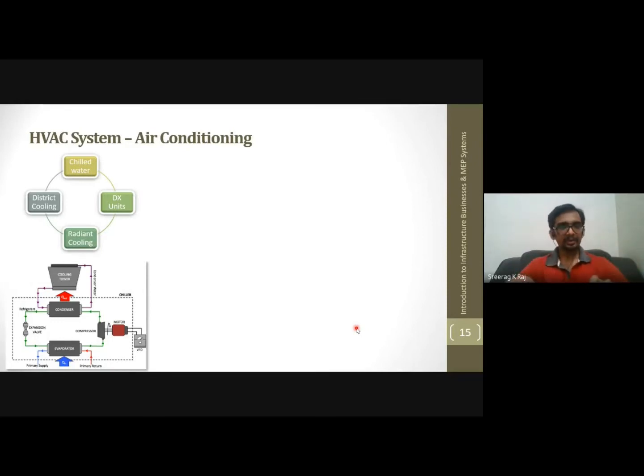The gas passes through a condenser where heat exchange takes place, like a vehicle's radiator - the same gas passes through different fins, and sometimes there will be fans so the heat is dissipated to the air, or there will be a separate loop of water connected to a cooling tower used to dissipate the heat from the condenser. So when heat is dissipated, the refrigerant will be at a lower temperature. Then when this refrigerant passes through an expansion valve, the temperature drops further, so it becomes very chilled.